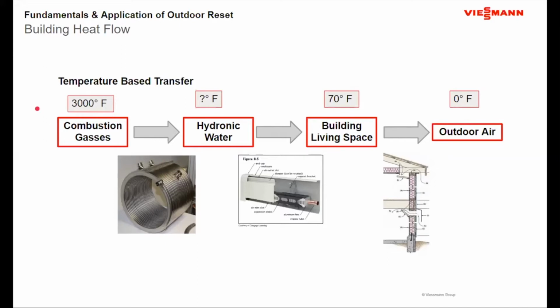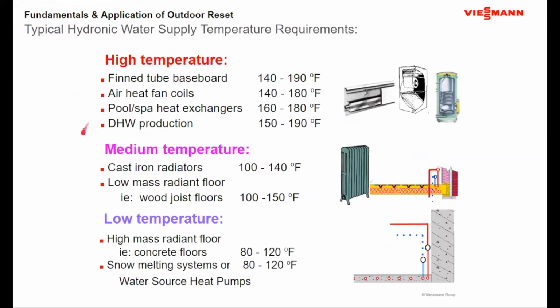Now, as far as the choice for water temperature, there's a lot of temperatures that people will normally throw in my direction when we talk about designing systems. A lot of times they'll say, well, is it going to be low, medium, or high temperatures? Low temperatures, generally, most people say somewhere under 120 degrees. Medium, probably 140 to 150 on the high side. The higher temperature ones, those are in the 180 to 190 degree range. So if I'm doing high temperature, a lot of people look at doing finned tube baseboard or an air handler unit at your high temperature.